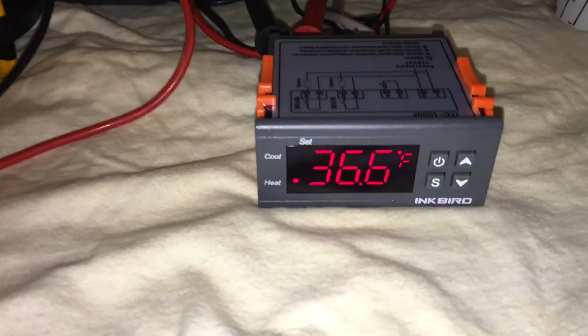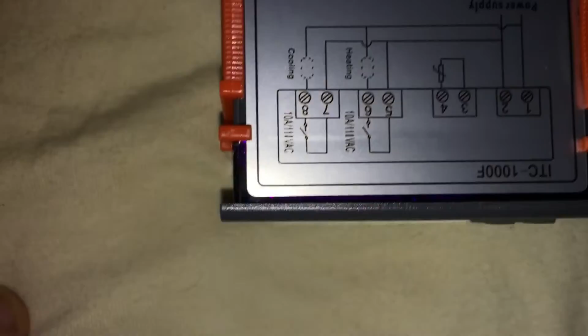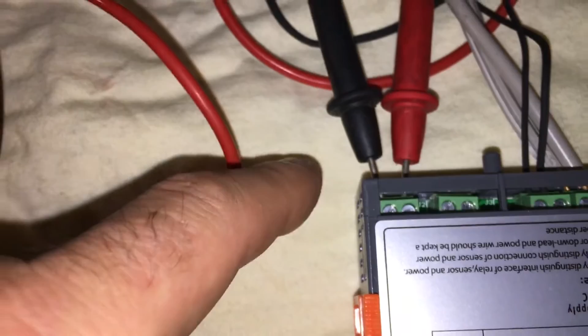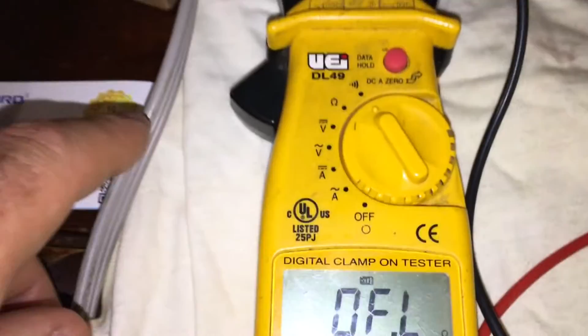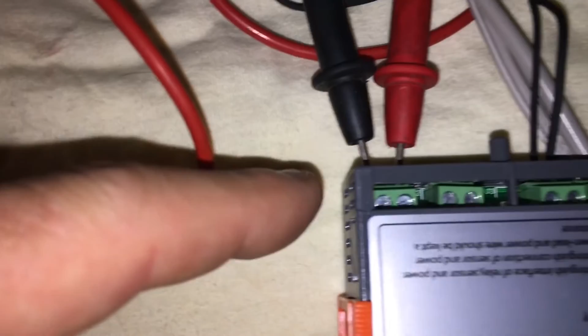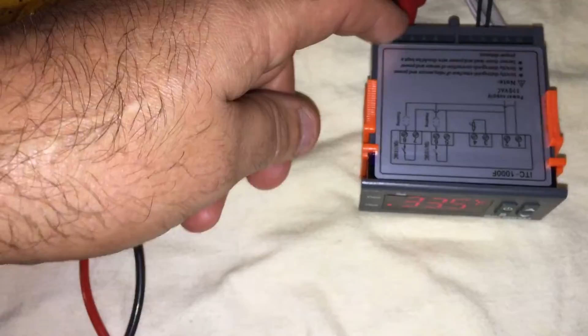More with the INKBIRD controller. So, I've got it all wired in, and what I have going on here is these are the cooling set of contacts right here. Just a set of contacts, 7 and 8. So basically what I did is I just put my meter on ohms. So this is on tone. So right now the contacts are open. So when those contacts close, the meter will tone. Easy way to check your meter.